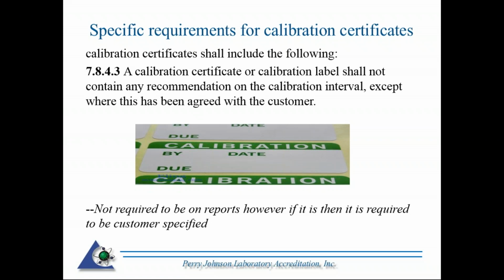7.8.4.3, this is something I would say a few times a year I get questions about regarding this requirement. A calibration certificate or calibration label shall not contain any recommendation on the calibration interval except where this has been agreed to with the customer. So in other words, if you have an instrument calibrated and you want a recalibration done after a set period of time, you can call it a due date, a recall date. The actual requirement of having that on the report is not required. However, if it is on the report, it needs to be customer specified. So if the customer specifies they want a calibration due date of annual, 1 year, it can be put on the report, and it has to be customer specified. That is something the lab cannot dictate.